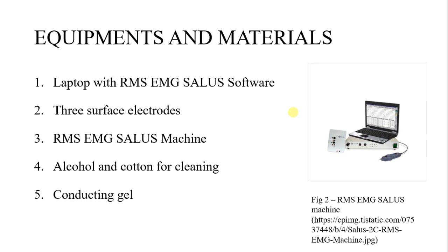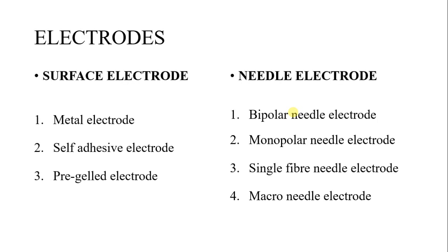There are two types of electrodes used. First are surface electrodes, which are non-invasive, and second are needle electrodes, which are invasive. The three most commonly used surface electrodes are metal electrodes, self-adhesive electrodes, and pre-gel electrodes. Needle electrodes include bipolar electrodes, monopolar needle electrodes, single fiber needle electrodes, and macro needle electrodes.